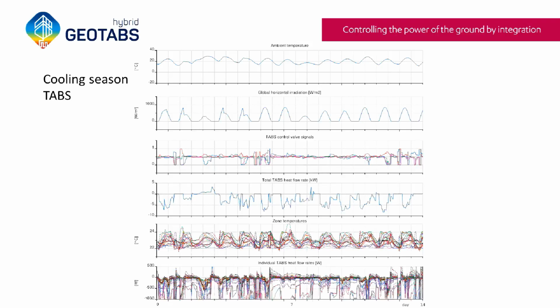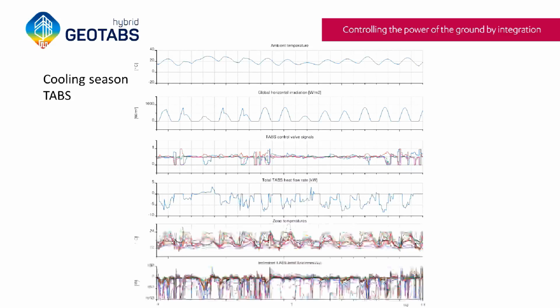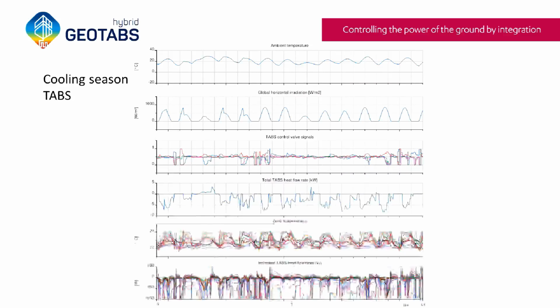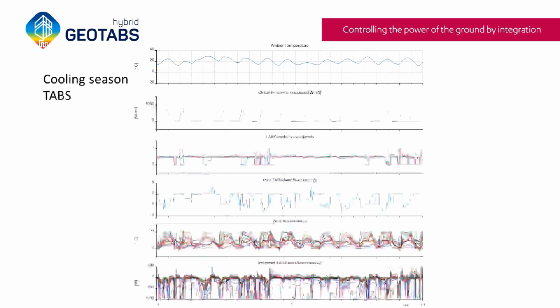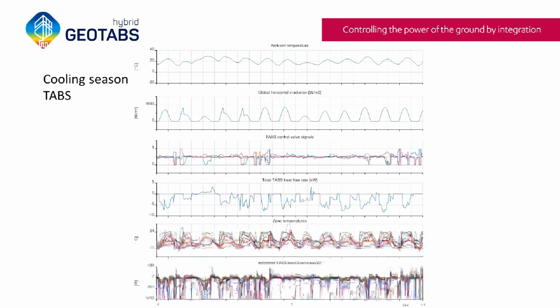And you see here that we're in cooling mode since the TABS thermal powers are now negative. What is also important to note is that the zone temperatures are now going up more. So we really need the cooling capabilities of the concrete core activation to stay below this 24 degrees C limit.